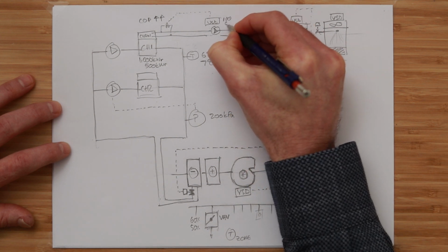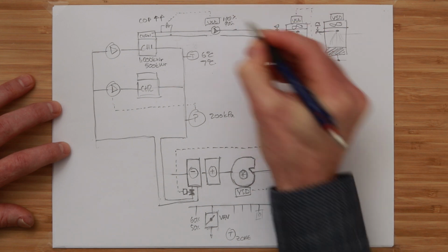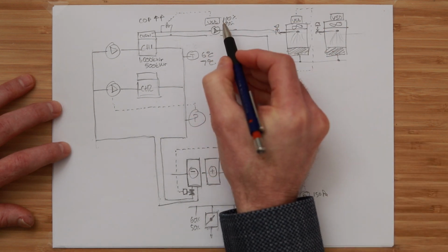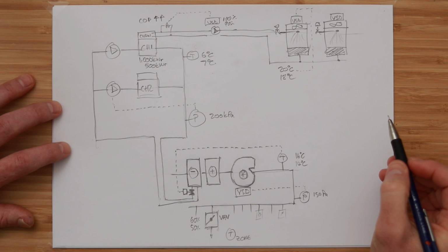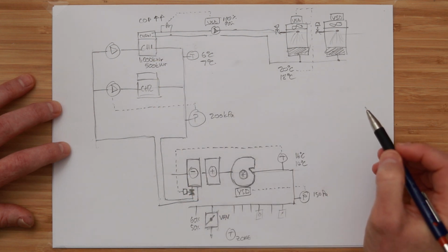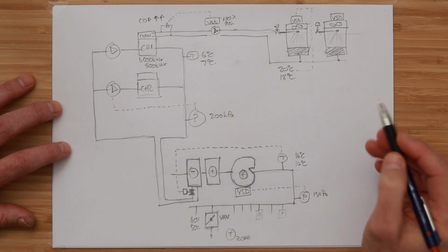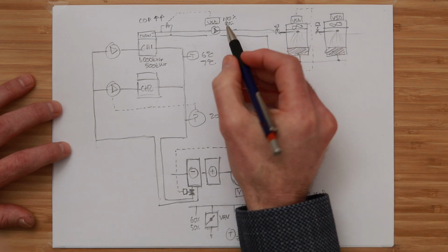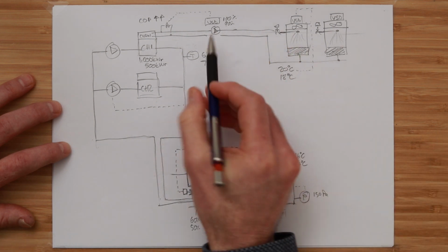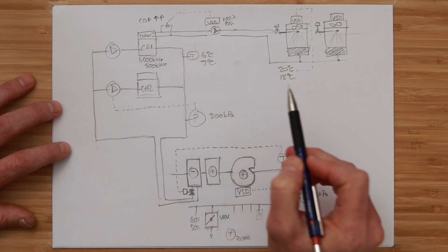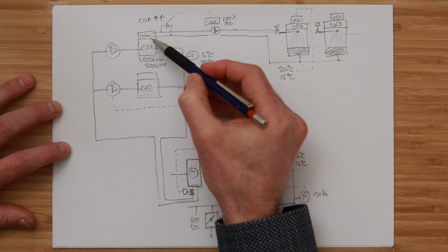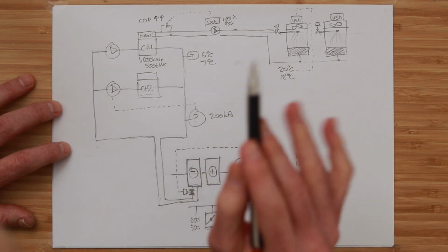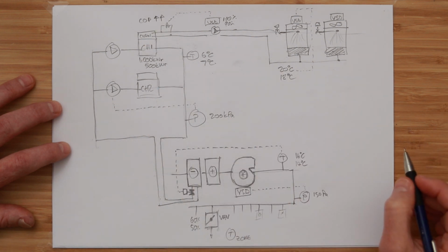Maybe we'd slow it down just 10%. So we can save energy on our condenser water pumps if our chillers don't need full design heat rejection. Again, the negative impact is that as this pump slows down, we have less volume of water through the condenser and there's less heat rejection. So it probably affects the COP of the chiller as well.